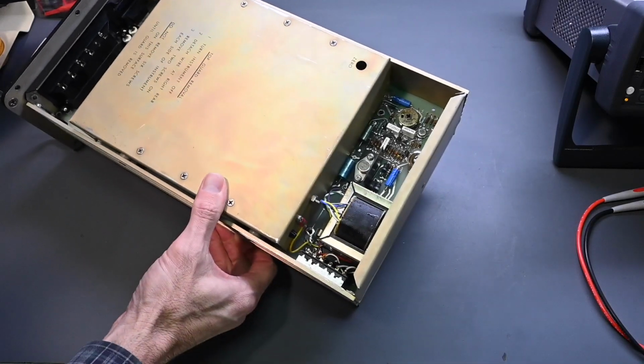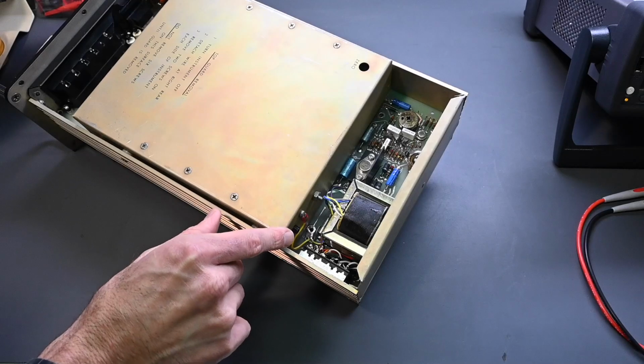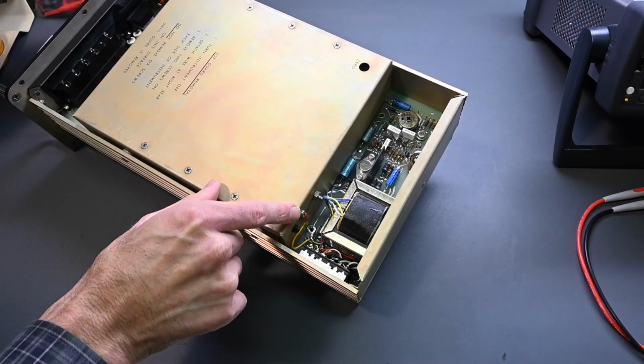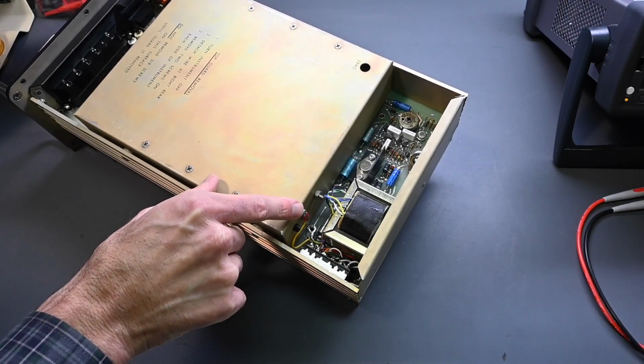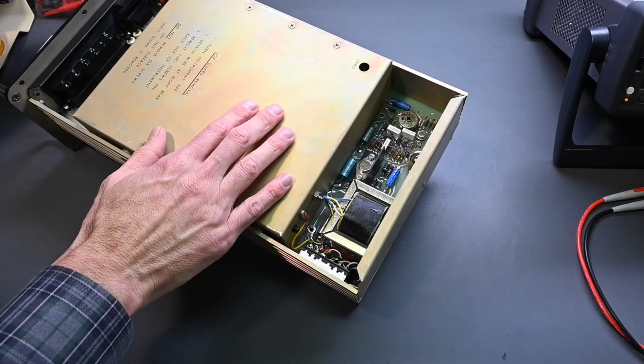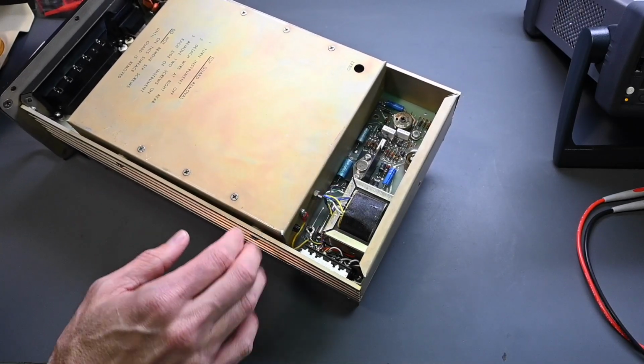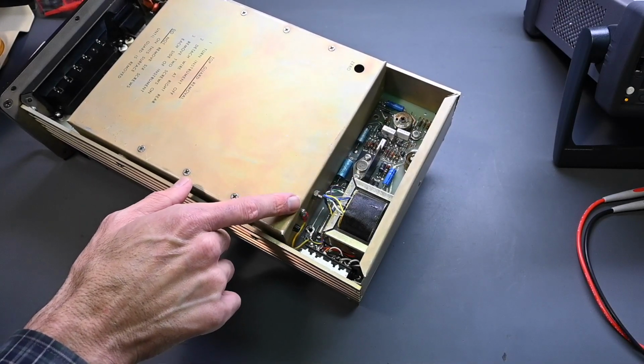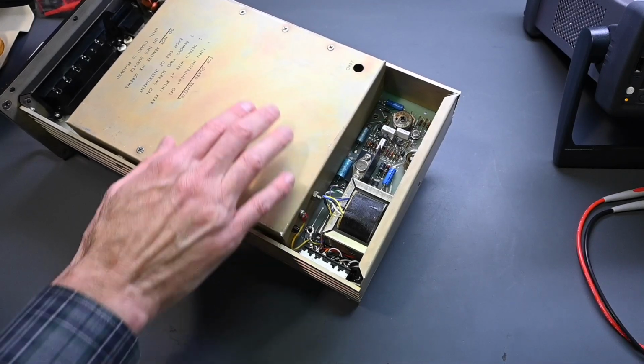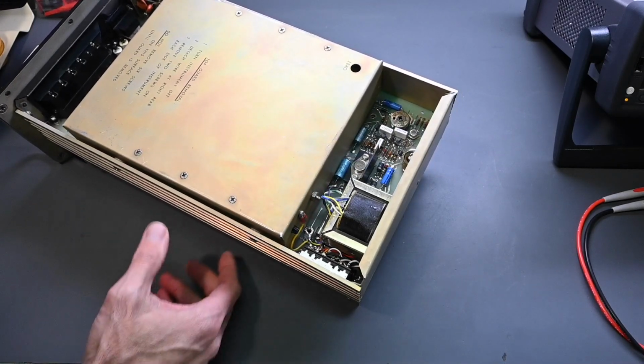And then in this corner right here, you can see there's a yellow wire that comes up and it attaches right there. So that's the only electrical connection that this shield has to the circuitry. And again, that's not a ground connection on the shield. That's a floating connection within the circuitry of the multimeter.